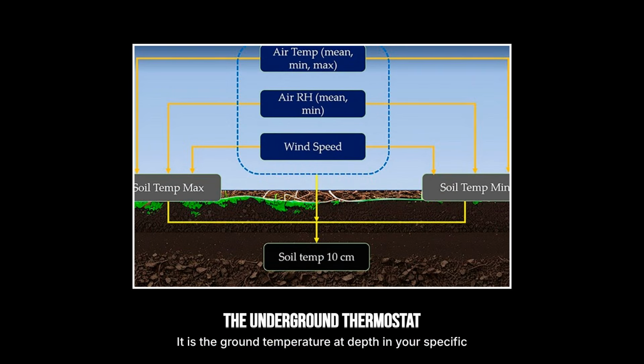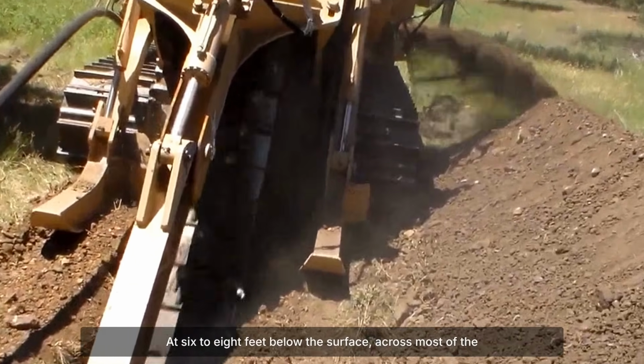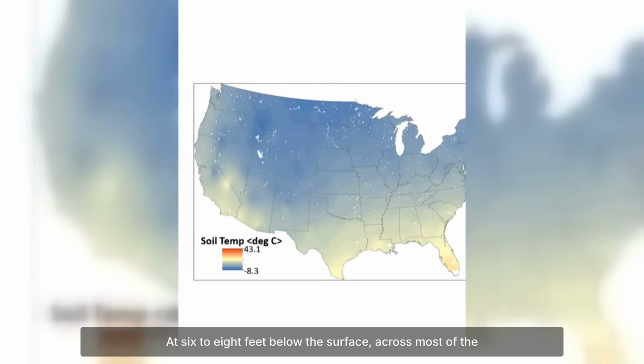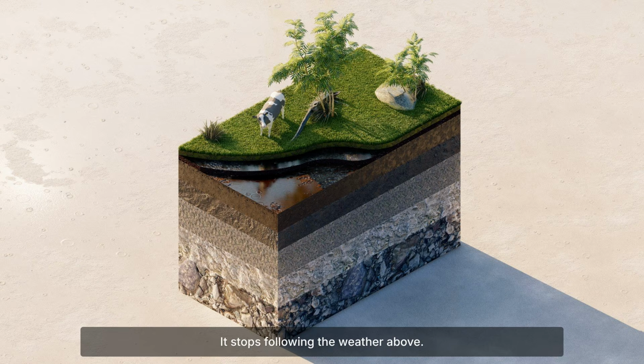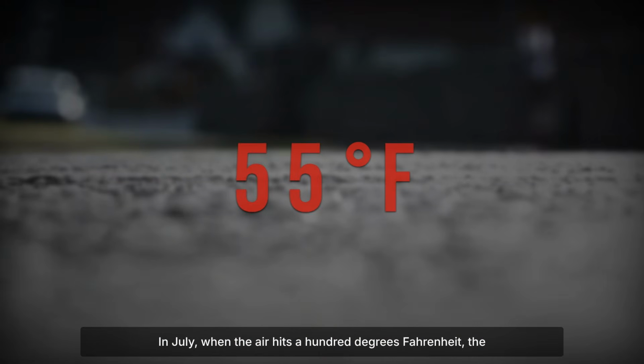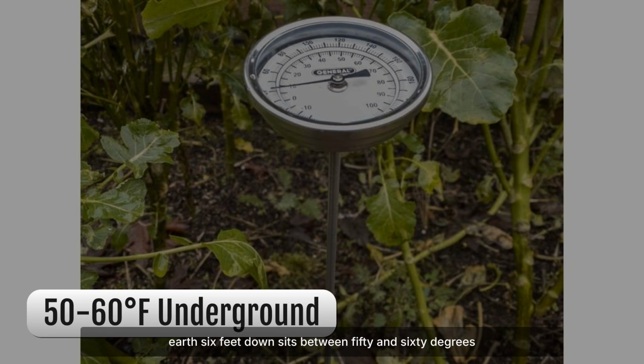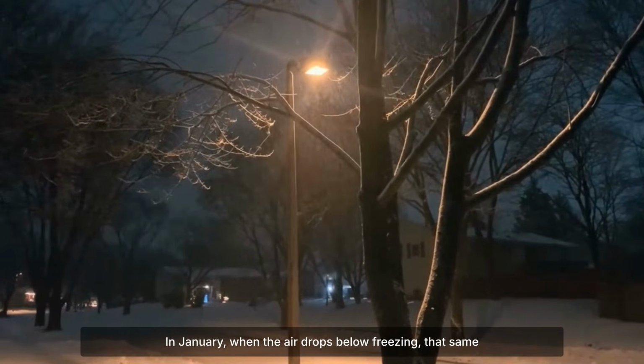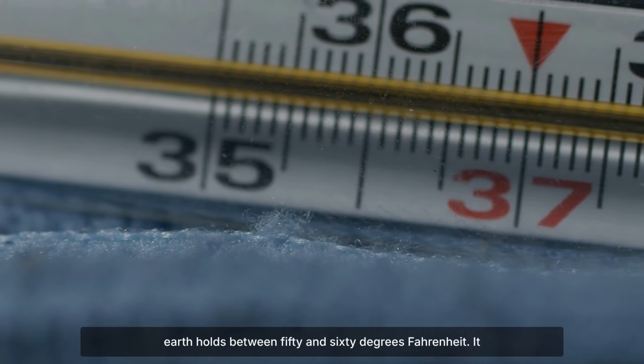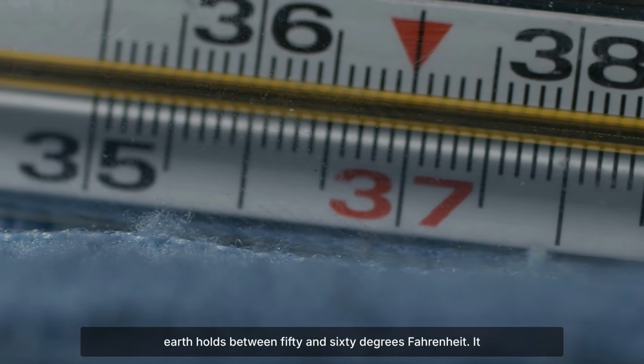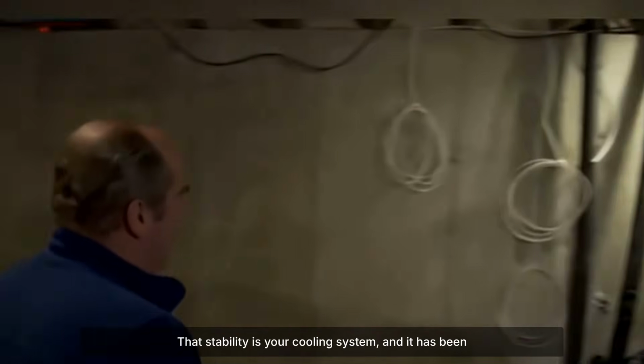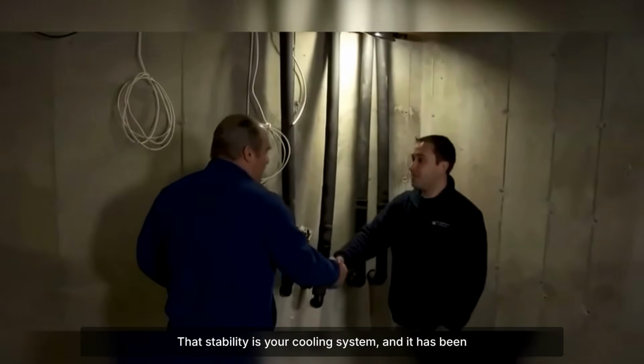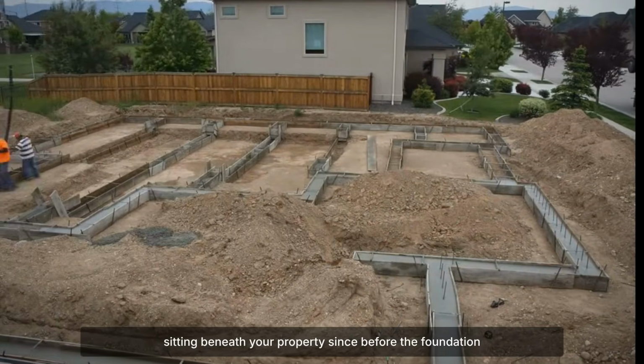It is the ground temperature at depth in your specific climate zone. At 6 to 8 feet below the surface, across most of the continental United States, the soil temperature stabilizes. It stops following the weather above. In July, when the air hits 100 degrees Fahrenheit, the Earth 6 feet down sits between 50 and 60 degrees Fahrenheit. In January, when the air drops below freezing, that same Earth holds between 50 and 60 degrees Fahrenheit. It never changes. That stability is your cooling system, and it has been sitting beneath your property since before the foundation was poured.